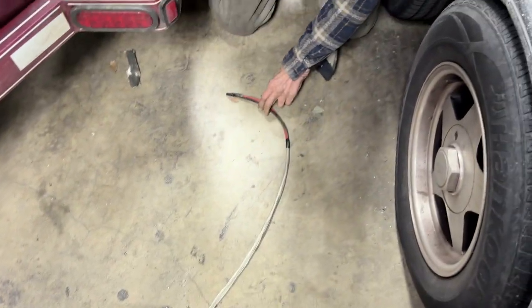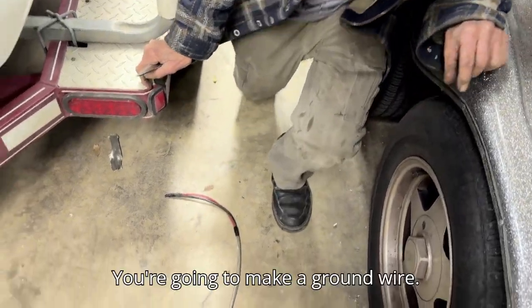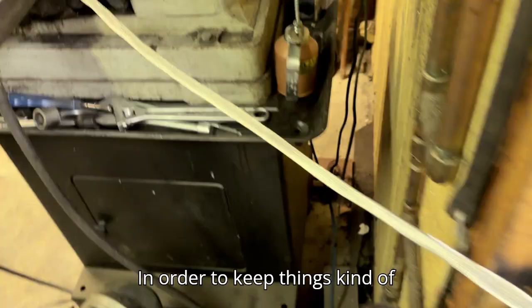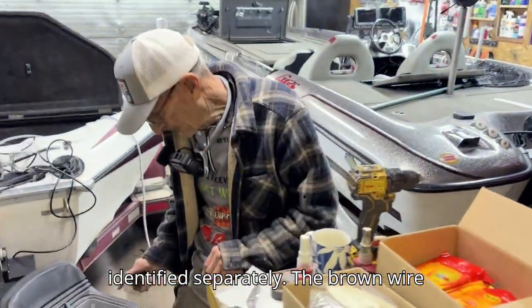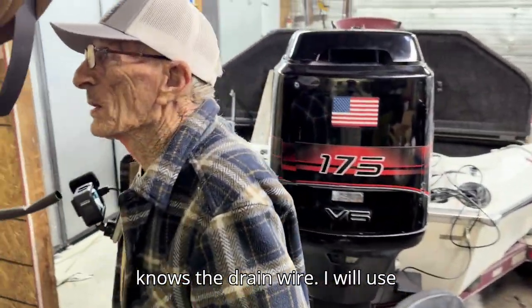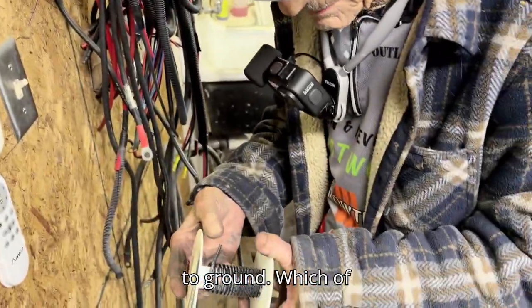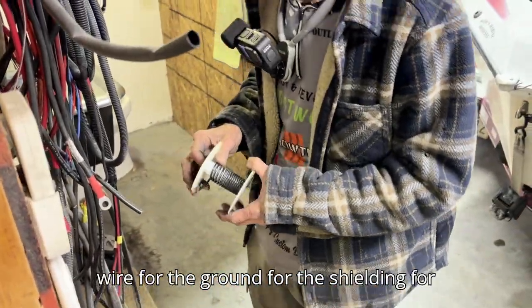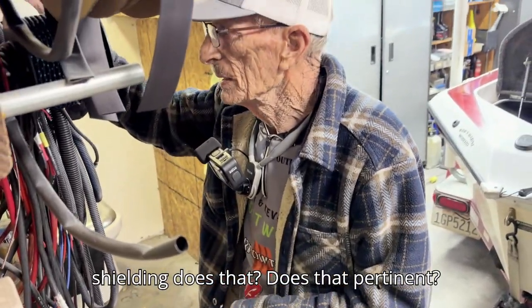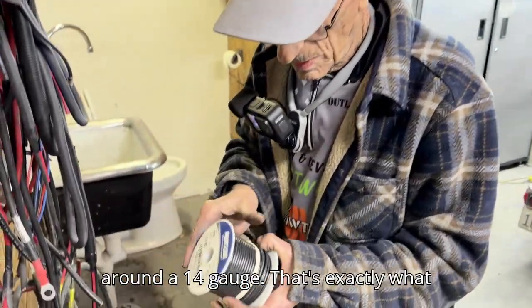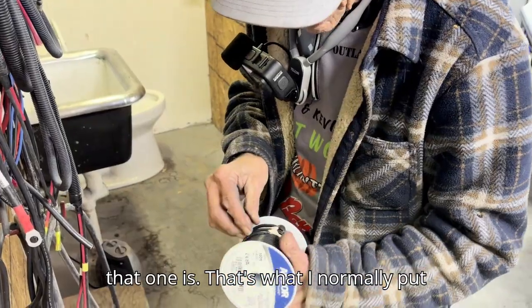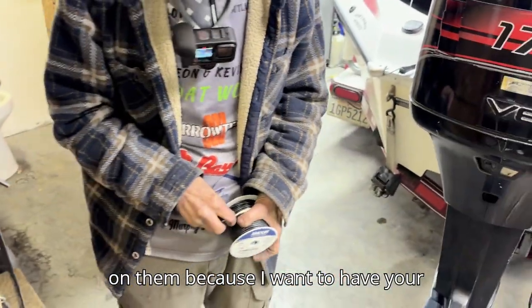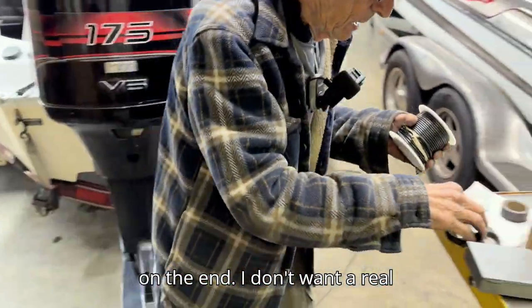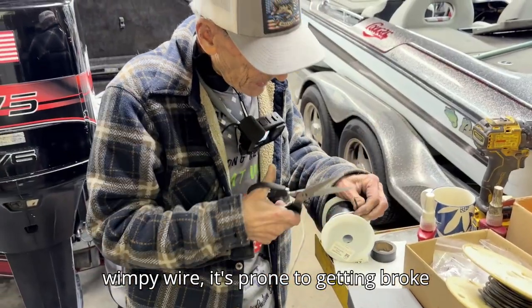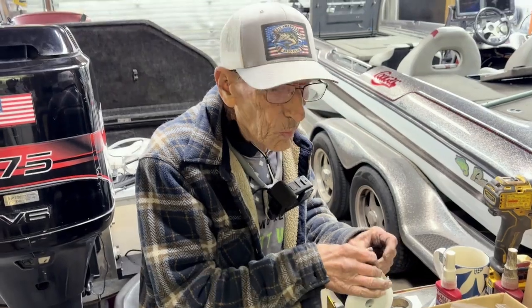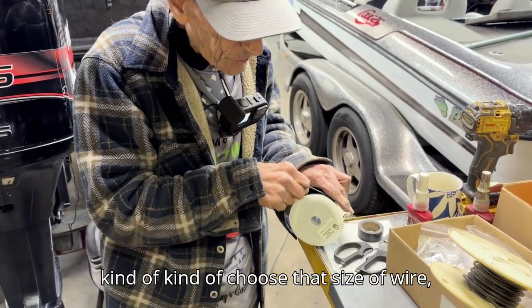Now I'm gonna make a ground wire. To keep things identified separately, the brown wire is known as the drain wire, and I'll use a small black wire for the shield ground. The gauge of wire for the shielding ground isn't a big deal, but I like around 14 gauge. That's exactly what that one is, and that's what I normally put on them, because I want a heavier wire and a heavier connector to terminate on the end. I don't want a wimpy wire prone to breaking or a wimpy connector that doesn't work well. That's why I choose that size of wire.